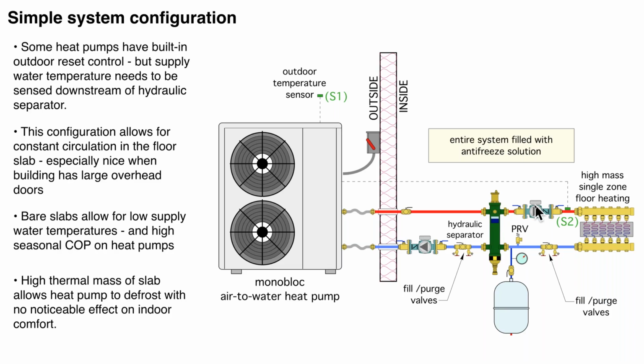Now, on the other side of the separator, we have another circulator just going to this high mass floor system. And I'm just showing a single manifold. It could be multiple manifolds if it's a large facility. You're probably not going to bring all those tubing circuits back to a single manifold, but you may have multiple manifolds. They might all be controlled as a single zone though.